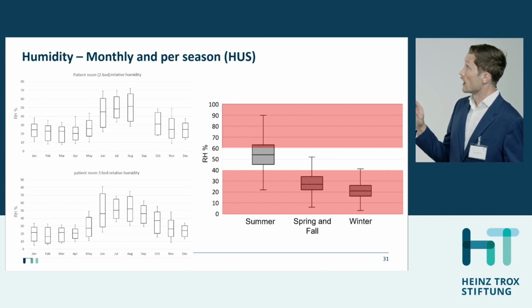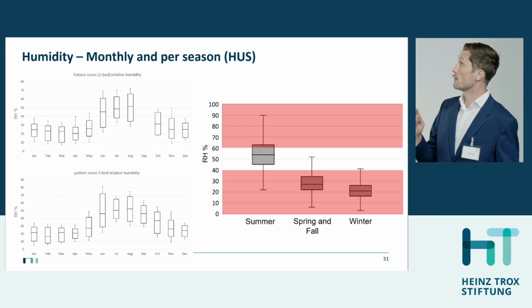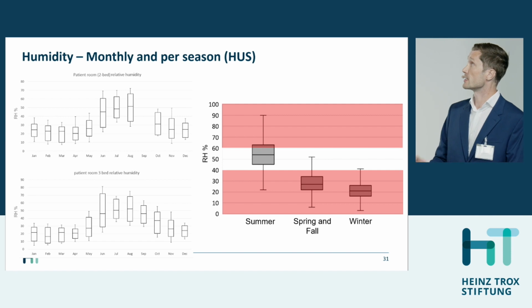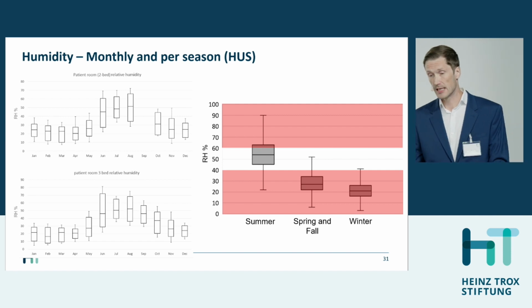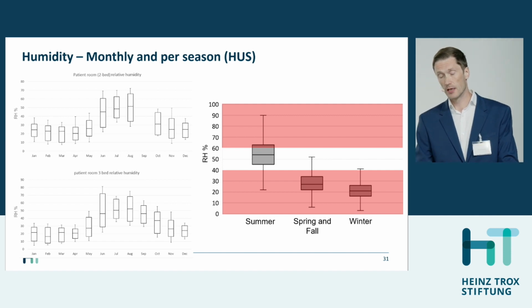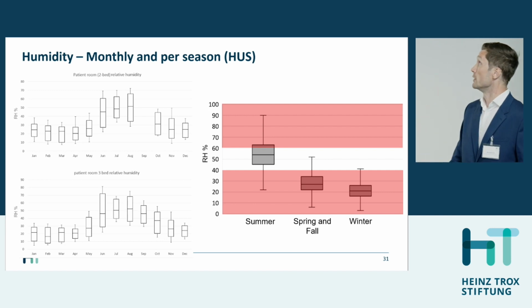But during summertime, we see a lot higher relative humidity inside the rooms. So basically this was caused because there was no humidification in the whole hospital. So the temperature, the relative humidity actually varied according to outdoor humidity. So that caused the changes in the humidity.